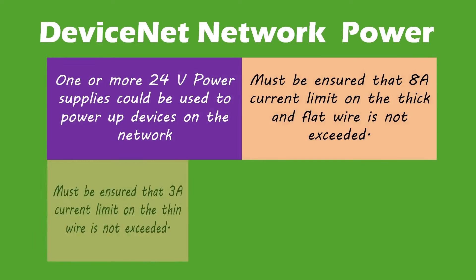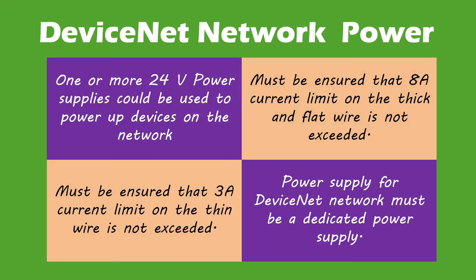One or more 24V power supplies can be used to power devices on a DeviceNet network. While powering up the network, it must be ensured that the 8 ampere current limit on thick or flat wire and the 3 ampere limit on thin wire is not exceeded. The power supplies used must not be used for any other purpose — they should be dedicated to the DeviceNet network only.